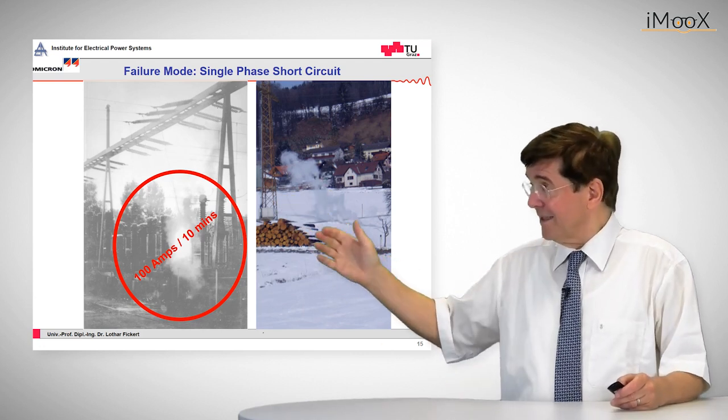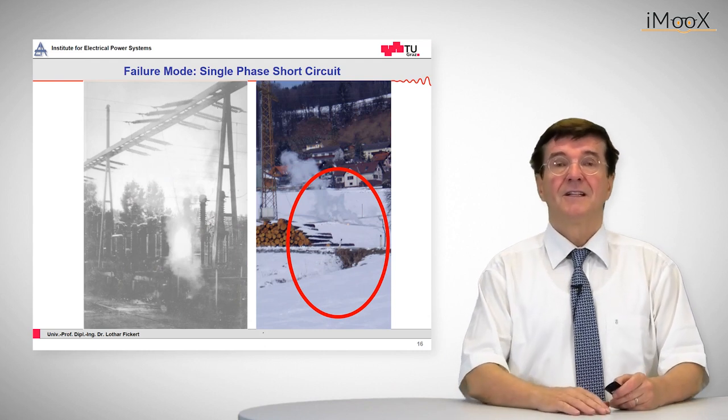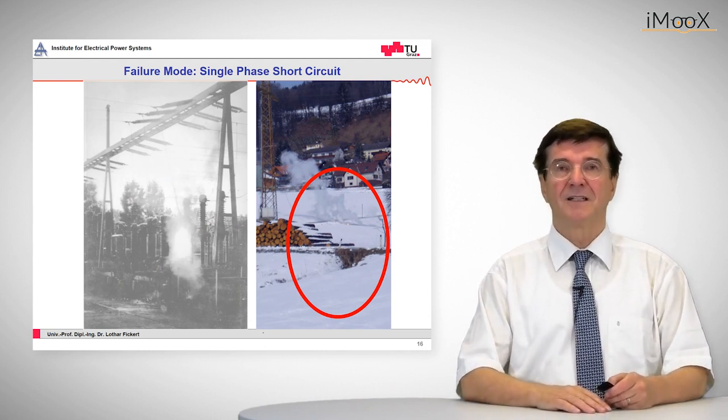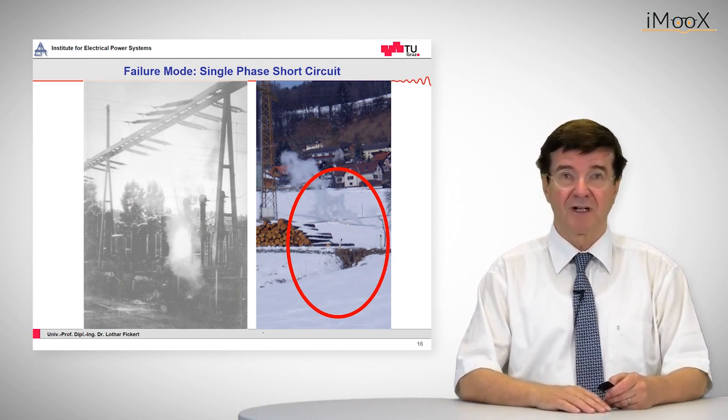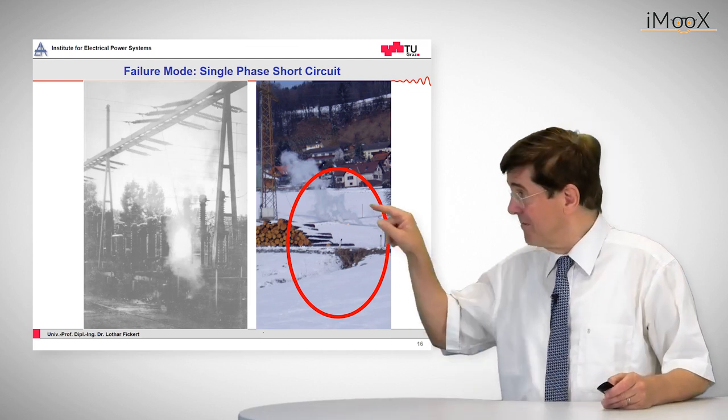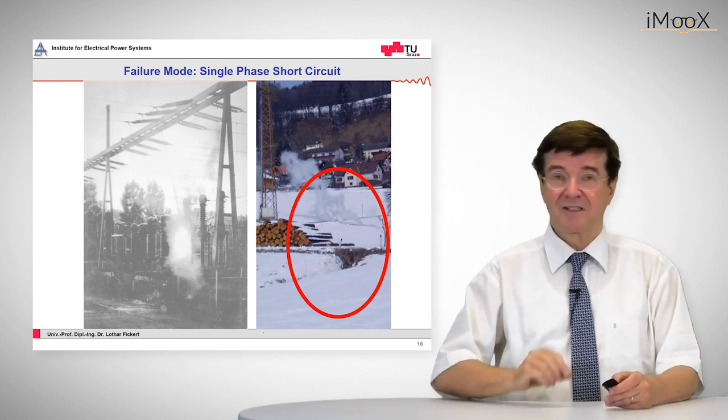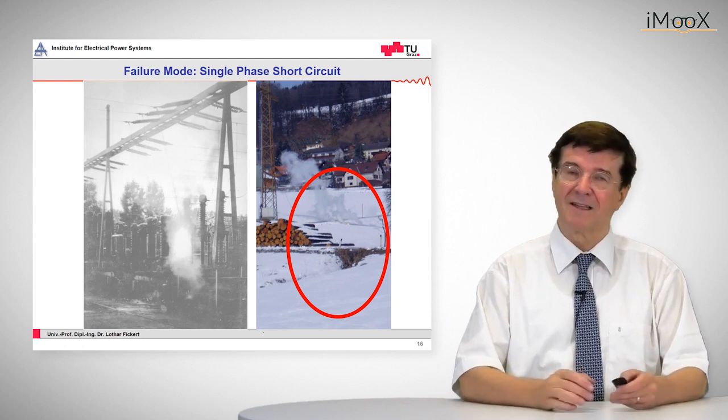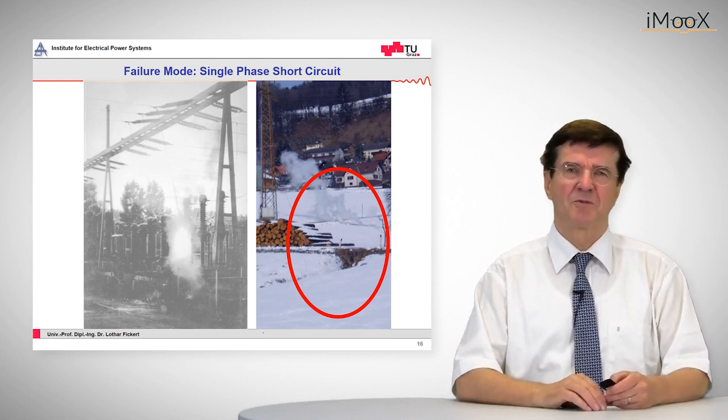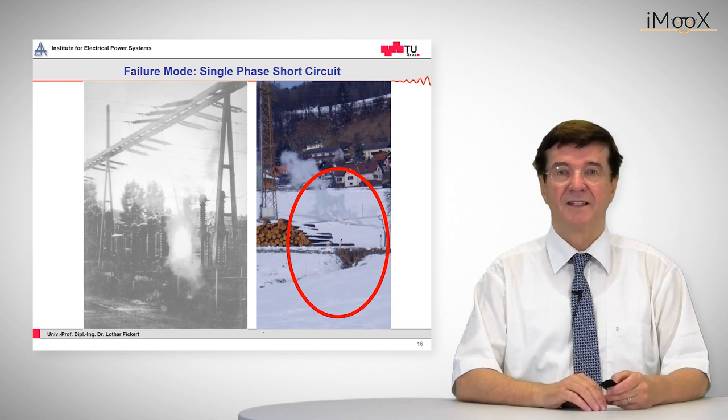Also to our right side we see a fault in an overhead line system where a conductor has broken and fallen down to ground and if you look carefully into the middle of this red circle you see a white blot. This is where the arc burns and again this arc is assumed to burn with approximately 100 amps and that has already gone on for quite a long time.